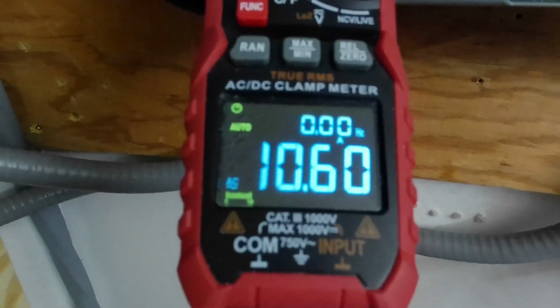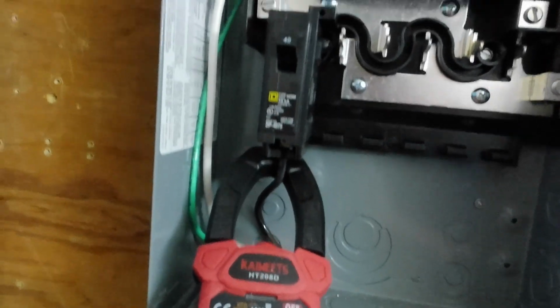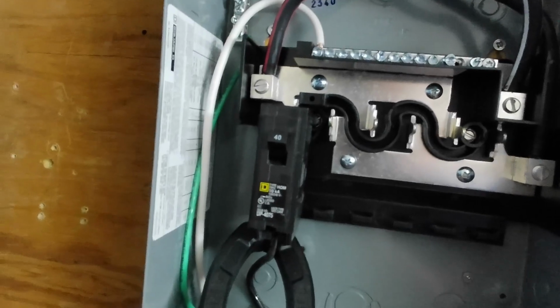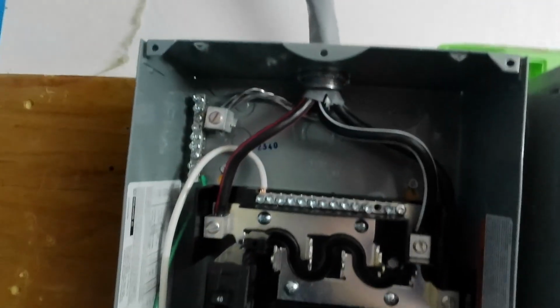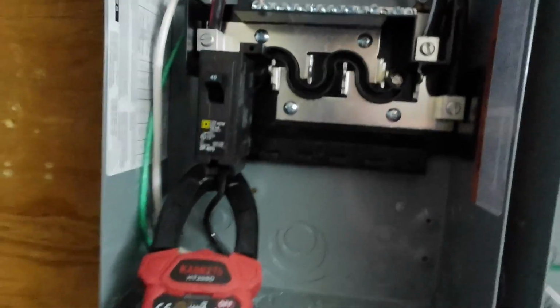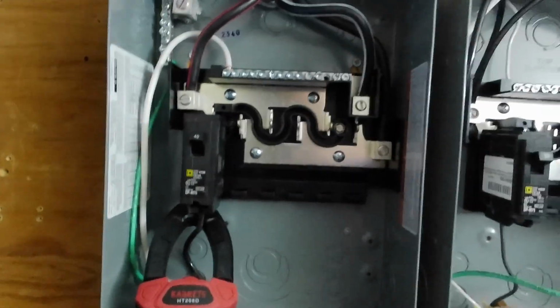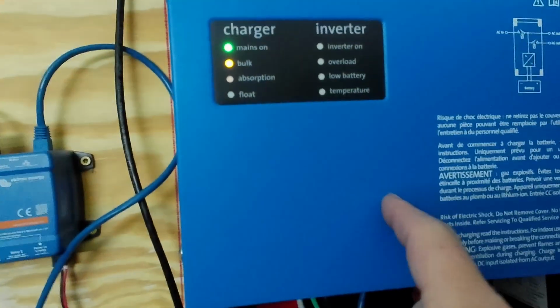Right now it's pulling 10 amps through this breaker. This breaker is set up for 40 amps, and this is my sub panel. So this feeds electricity into this room so that I can then distribute that electricity through this Multiplus.